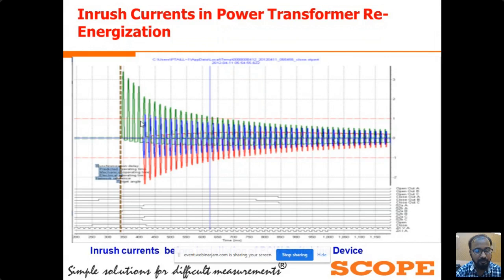Without any control switching device, we have observed this type of inrush current during the energization of the power transformer. For the R phase, the inrush current value is near 2 times the full load current, and for the B phase it is near the full load current. Even without any load, only at the time of no load charging, we have observed this type of inrush current in power transformer application.